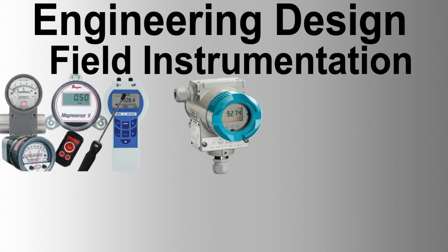Level. All level instrument process connections on vessels must be 2-inch flanged and 300 class as a minimum, with larger sizes for tanks using radar type. Instrument selection and installation must allow for removal and replacement without taking the vessel out of service. Instruments must have dedicated nozzles for connection, or standpipes may be provided if necessary. Each instrument must have full-bore isolation valves, and all externally mounted instruments must have 1-inch flanged drain and vent connections.